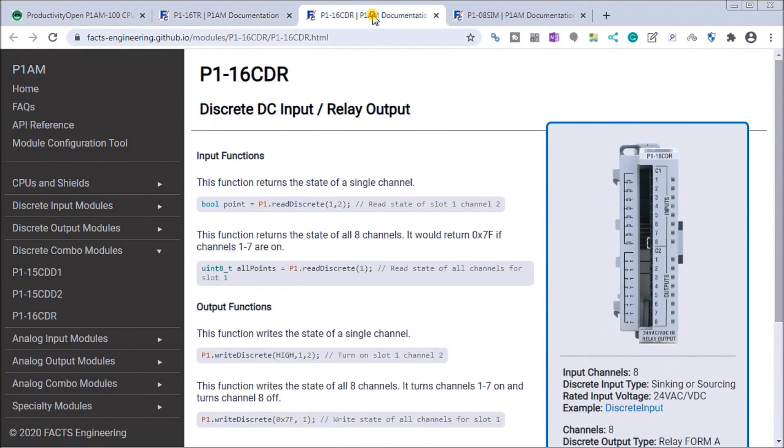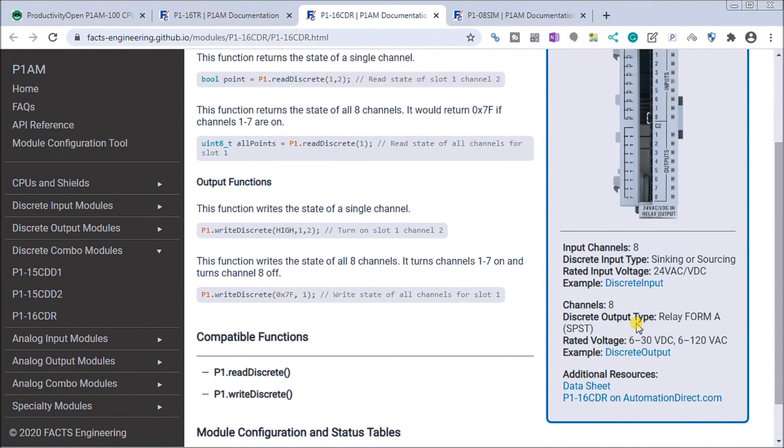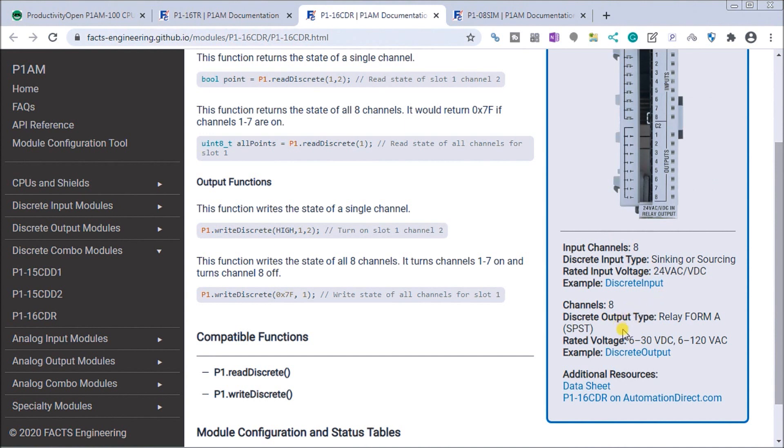Then we're going to add a combination card, a DC input and relay output. Our input channel has eight channels that are sinking or sourcing with rated input voltage of 24 volt AC or DC. We have eight channels output which is a relay, form A, single pole, single throw, with 6 to 30 volt DC or 6 to 120 volt AC output.